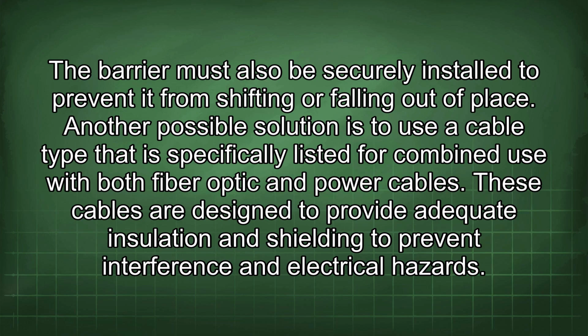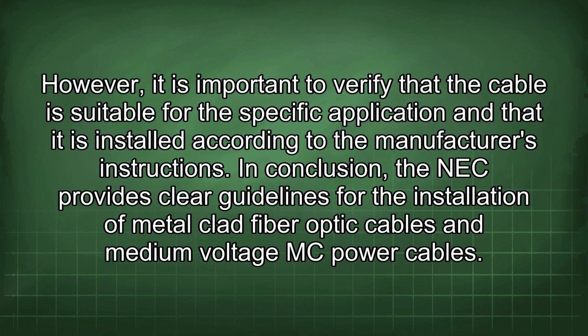Another possible solution is to use a cable type that is specifically listed for combined use with both fiber optic and power cables. These cables are designed to provide adequate insulation and shielding to prevent interference and electrical hazards. However, it is important to verify that the cable is suitable for the specific application and that it is installed according to the manufacturer's instructions.